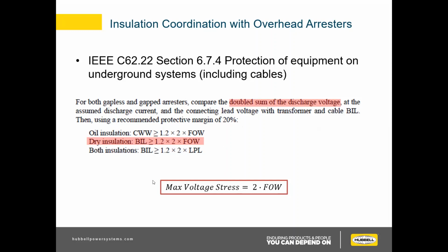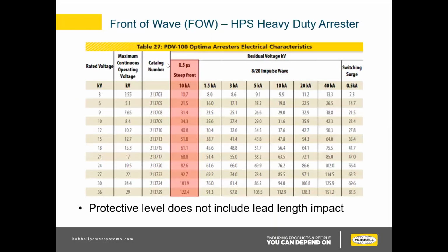With no elbow arrestor, the maximum voltage stress will be 2 times the front of wave. I haven't talked about that much, but a front of wave is just a wave shape that is possible to occur from nature. That's generally from a lightning strike, and it's a super fast rising wave. That's why you have such a voltage adder. That's listed here. This would be your 0.5 microsecond rise time, or your steep front wave. That means your front of wave. This is going to be the worst case scenario as far as discharge voltage for your arrestor, especially with regards to line lead length.